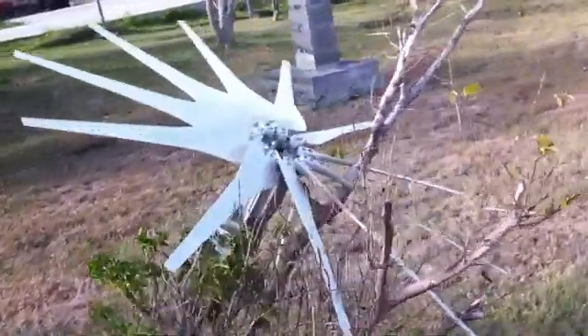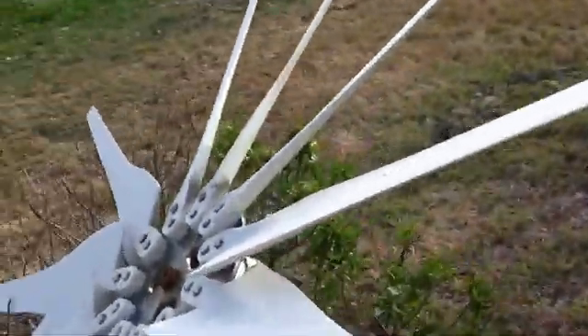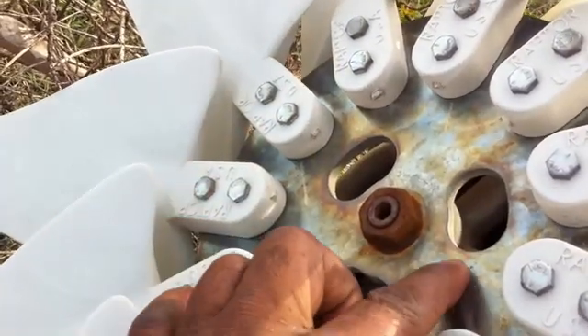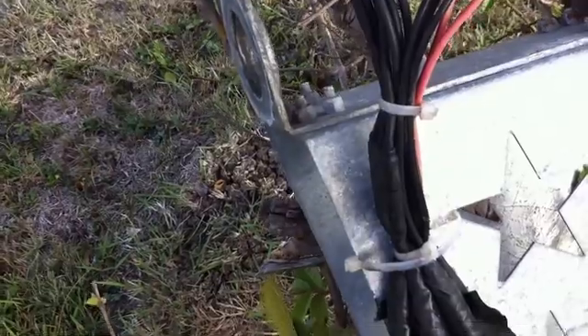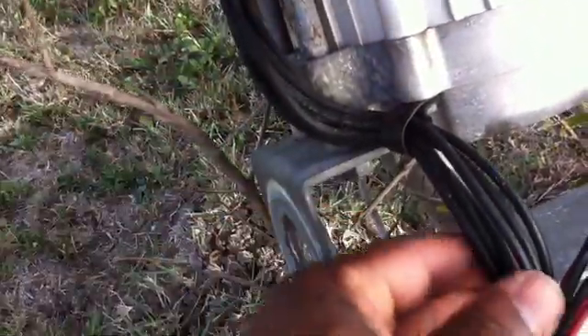We are going to just examine this a bit and clean it up. This has been up for a year and this is not really so much rust — the only thing rust is this nut here. We are going to fix that up. Otherwise this was still working; we just had to borrow that pipe. The pipe that this was using is a Schedule 80 pipe and I want to put that Schedule 80 right up top there.